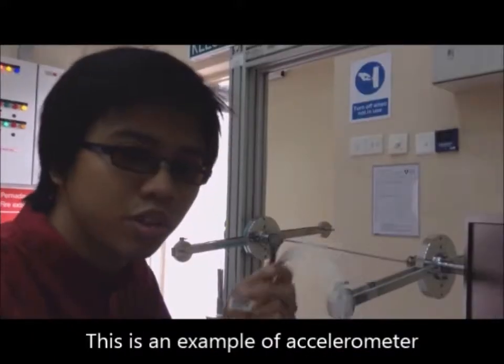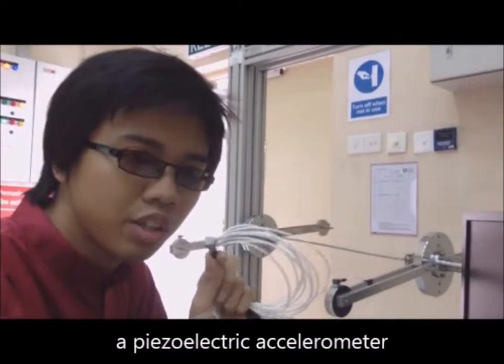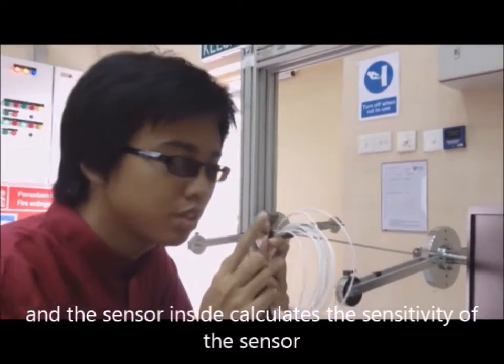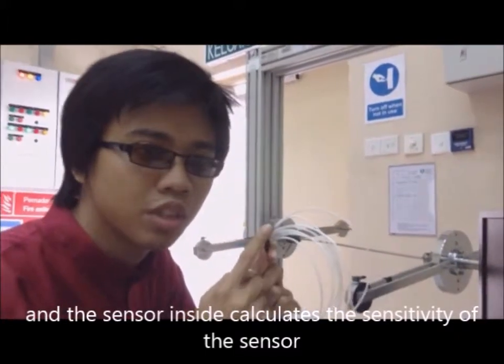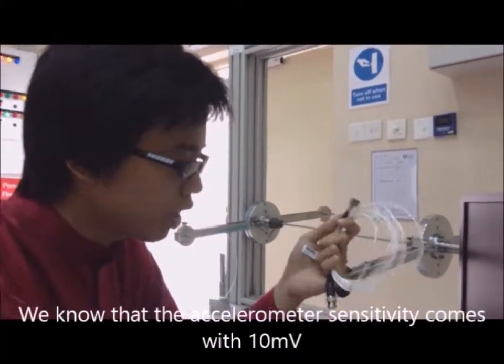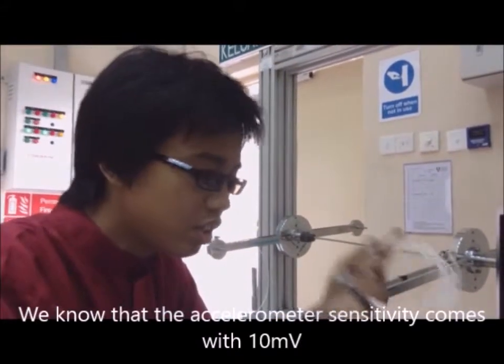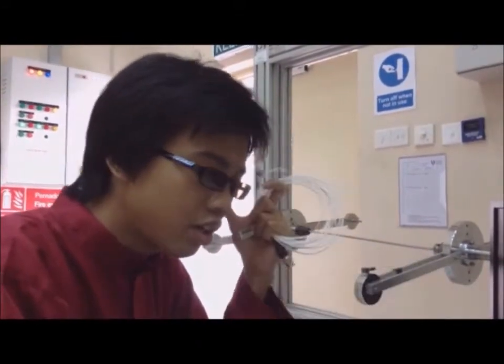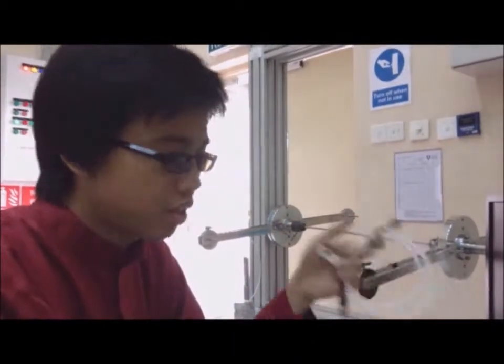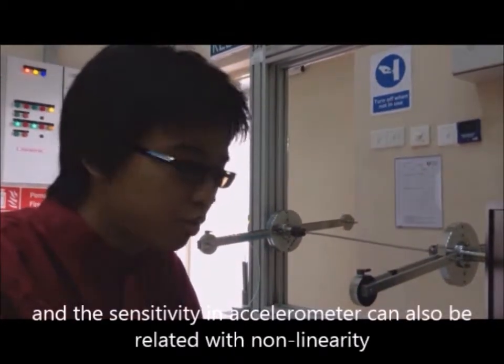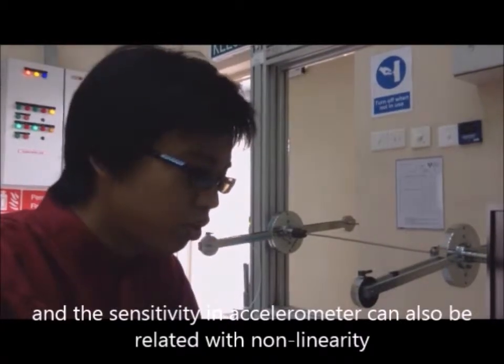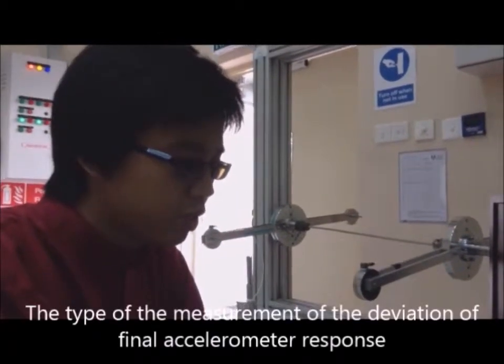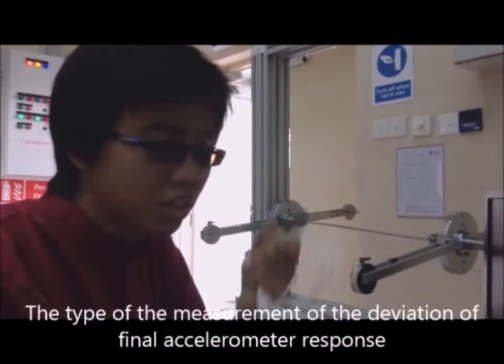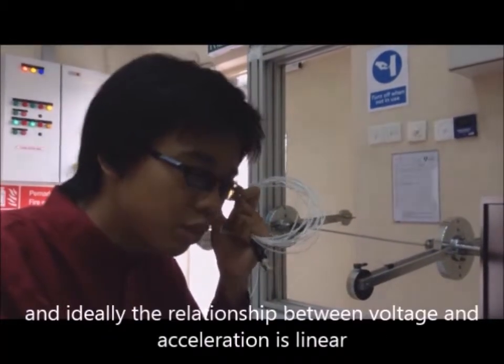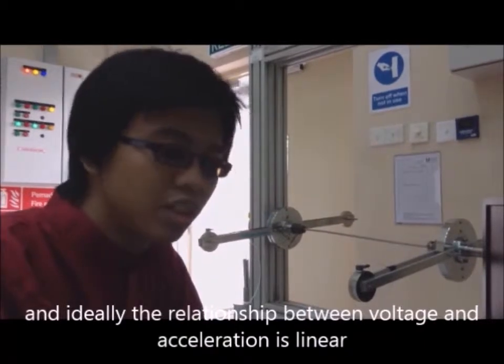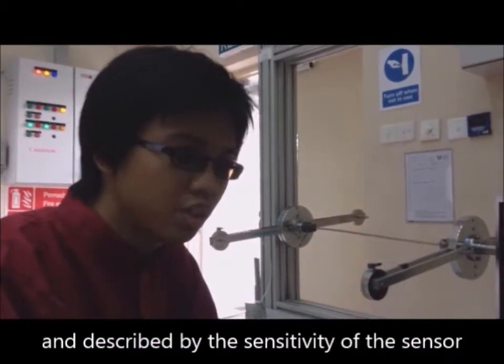This is an example of an accelerometer. This is a piezoelectric accelerometer. There is a sensor inside, which determines the sensitivity of the sensor. Usually we know that accelerometer sensitivity is 10 millivolt or 100 millivolt per gram. And we know that the sensitivity in an accelerometer can also be related to nonlinearity, a type of measurement of the deviation of an accelerometer response. Ideally, the relationship between voltage and acceleration is linear and described by the sensitivity of the sensor.